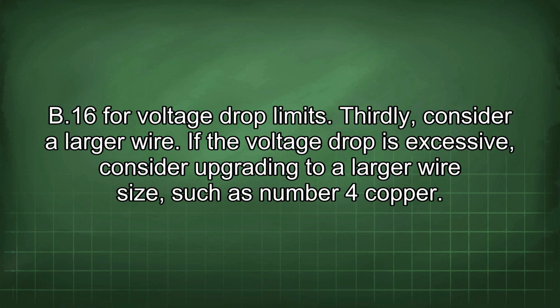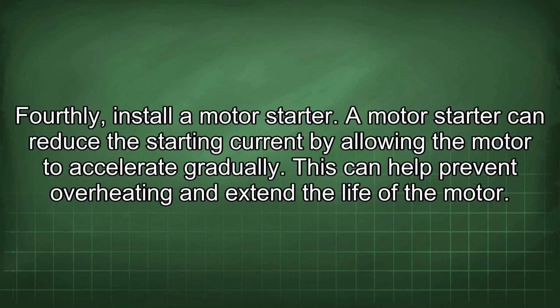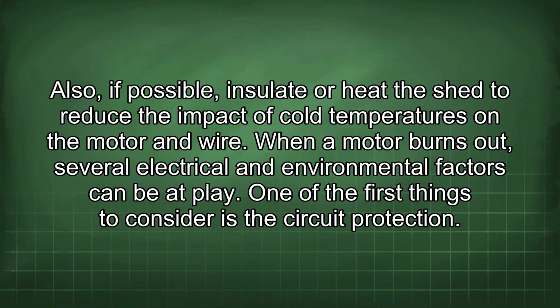Thirdly, consider a larger wire. If the voltage drop is excessive, consider upgrading to a larger wire size, such as number 4 copper. Fourthly, install a motor starter. A motor starter can reduce the starting current by allowing the motor to accelerate gradually. This can help prevent overheating and extend the life of the motor. Also, if possible, insulate or heat the shed to reduce the impact of cold temperatures on the motor and wire.